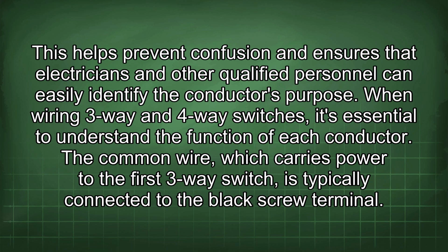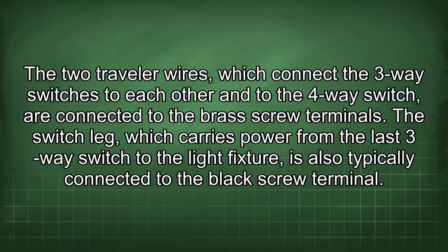When wiring 3-way and 4-way switches, it's essential to understand the function of each conductor. The common wire, which carries power to the first 3-way switch, is typically connected to the black screw terminal. The 2 traveler wires, which connect the 3-way switches to each other and to the 4-way switch, are connected to the brass screw terminals. The switch leg, which carries power from the last 3-way switch to the light fixture, is also typically connected to the black screw terminal.